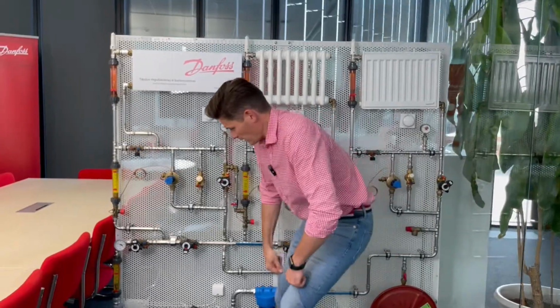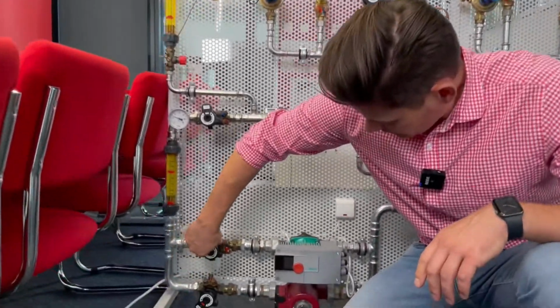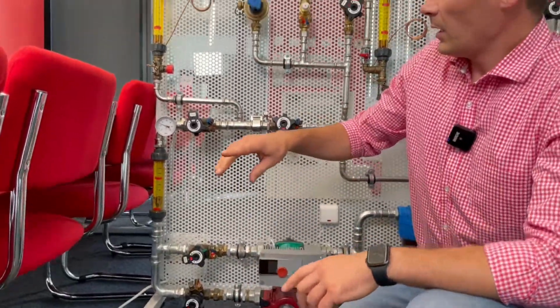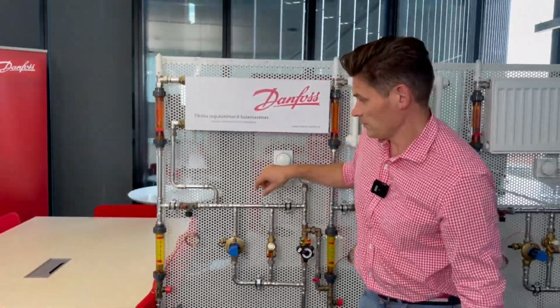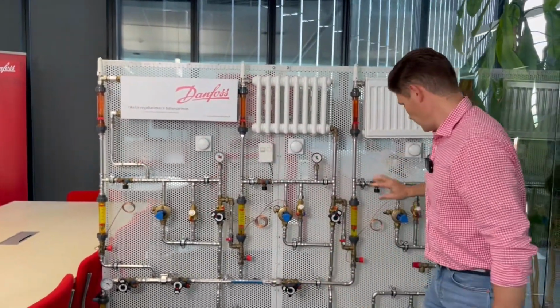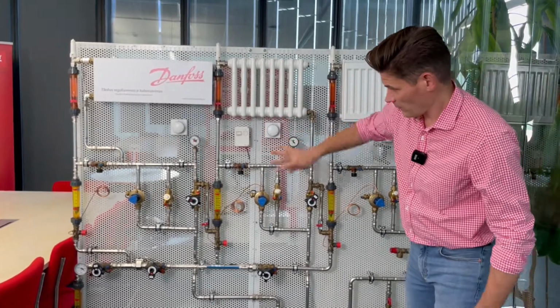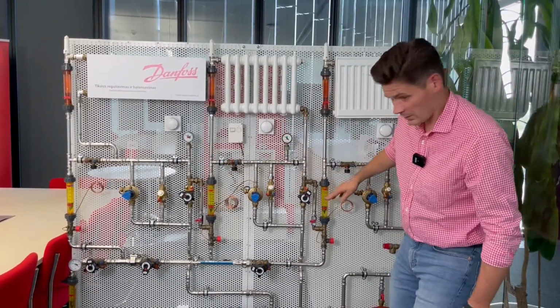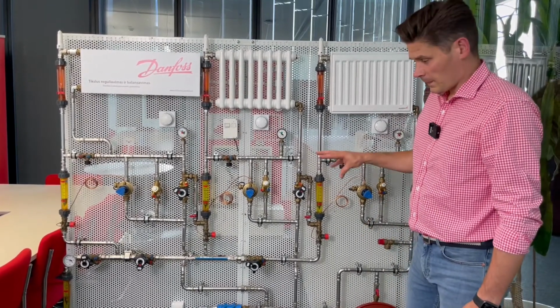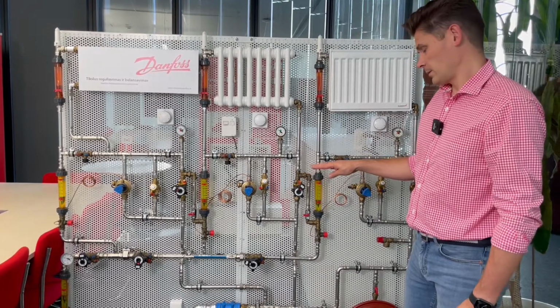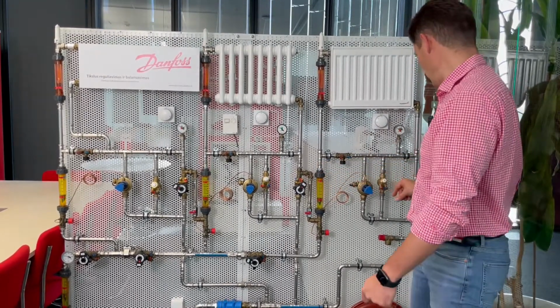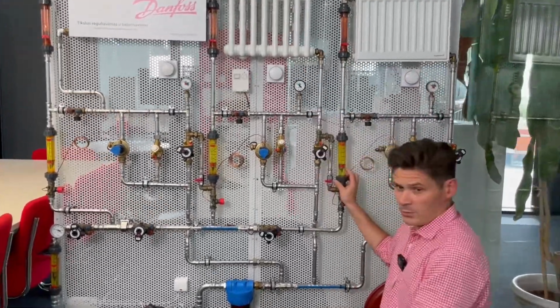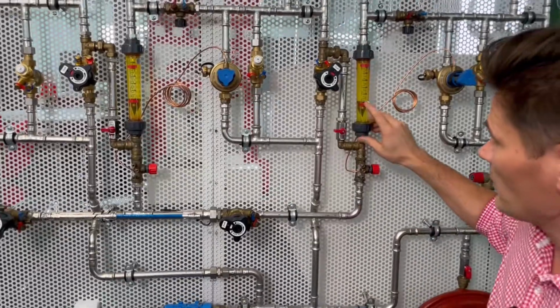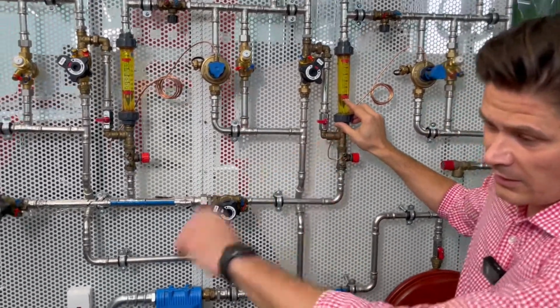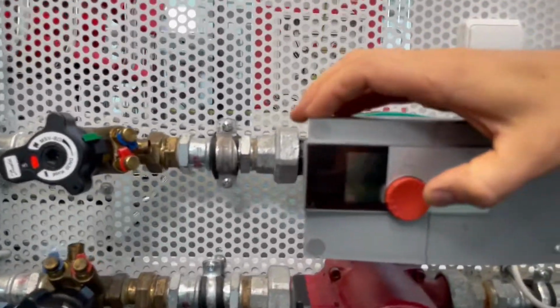Okay, let's switch to the automatic pump again. I close this 3-speed pump, open the automatic one, and open everything in the system to have flow everywhere. So I have 100, 100, and 100 liters everywhere, and now I need to make pump optimization. Okay, so we actually need two guys. One guy is checking how many liters we have at the last riser, and another guy goes to the substation and simply regulates the circulation pump.